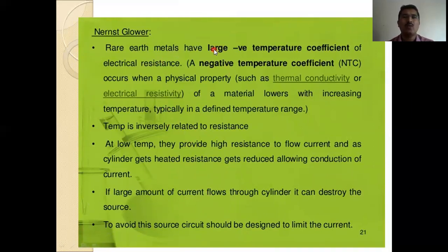Nernst glower, rare earth metals have large negative temperature coefficient of the electrical resistance. A negative temperature coefficient, that is NTC, occurs when a physical property such as thermal conductivity or electrical resistivity of the material lowers with increasing temperature, typically in a defined temperature range. Temperature is inversely related to the resistance. At low temperature, they provide high resistance to flow current, and as the cylinder gets heated, resistance reduces allowing the conduction of current. If large amount of current flows through the cylinder, it can destroy the source. To avoid this, a circuit should be designed to limit the current.